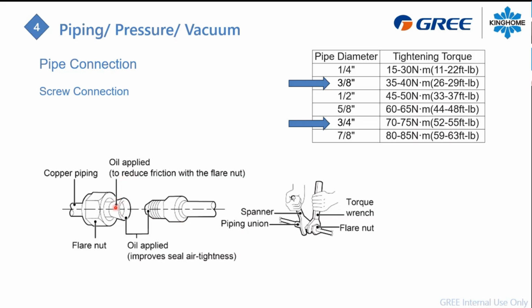If you apply a little bit of oil, just on the piping directly, that will help to reduce that friction. Also, when you do your piping, just make sure the piping is not attached too tightly to the house or the wall or anything, because this kind of unit, you will use it in cooling mode and in heating mode, so you can have a lot of movement from the piping. When the copper catches some heat, it will expand a little bit and it will contract a little bit when it's colder.